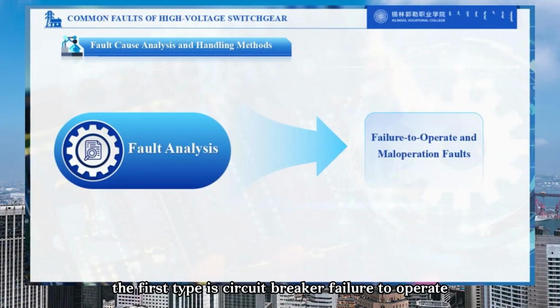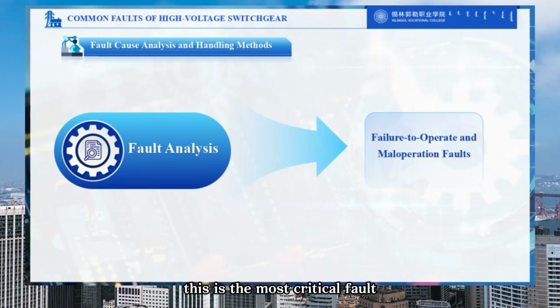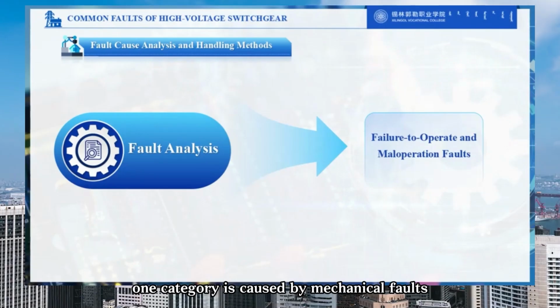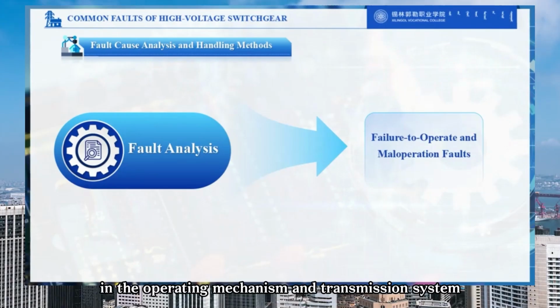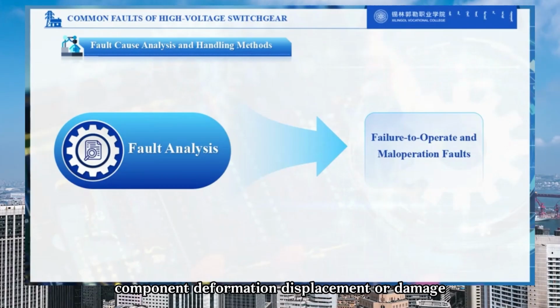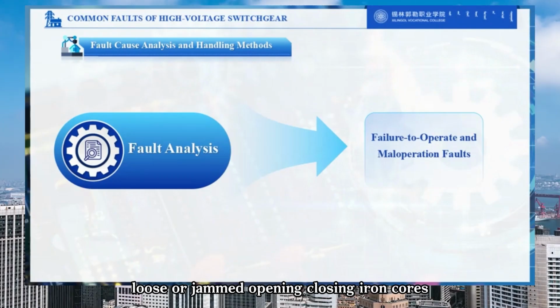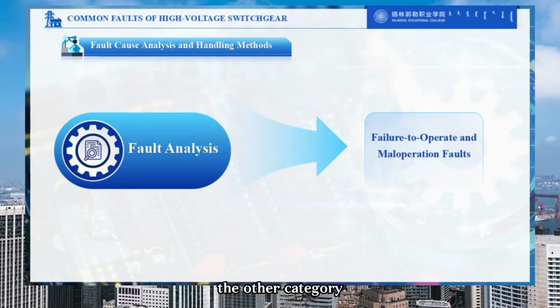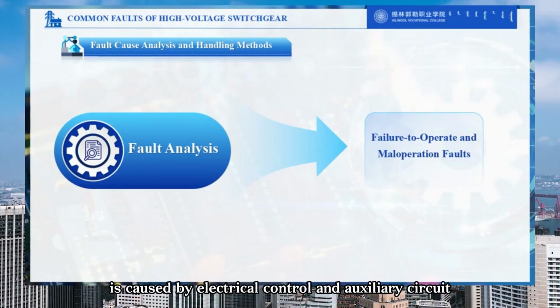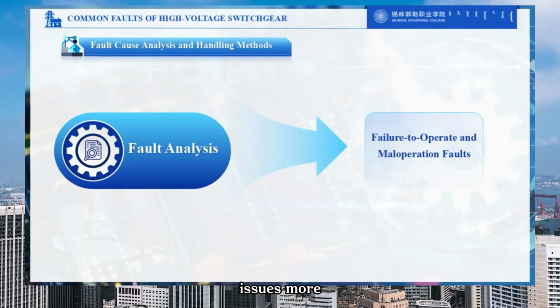The first type is circuit breaker failure to operate, refusal, or misoperation. This is the most critical fault in high-voltage switchgear. Its causes can be divided into two categories. One category is caused by mechanical faults in the operating mechanism and transmission system. Specific manifestations include mechanism jamming, component deformation, displacement or damage, loose or jammed opening and closing iron cores, loose shaft pins, trip failure, etc. The other category is caused by electrical, control, and auxiliary circuit issues.